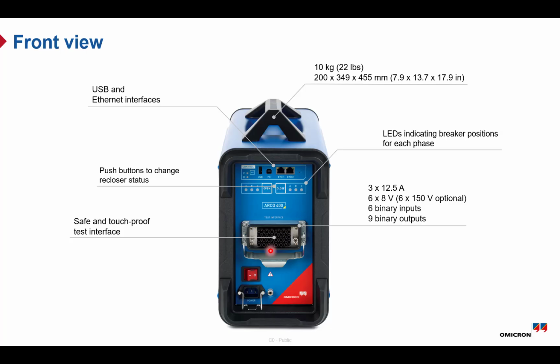For voltage, there are two ranges. A low range, up to 10 volts, for higher accuracy with low-level signals coming from the low-power voltage transformer, and a higher range up to 150 volts for conventional voltage inputs. This allows flexibility depending on the type of sensors used in the recloser.